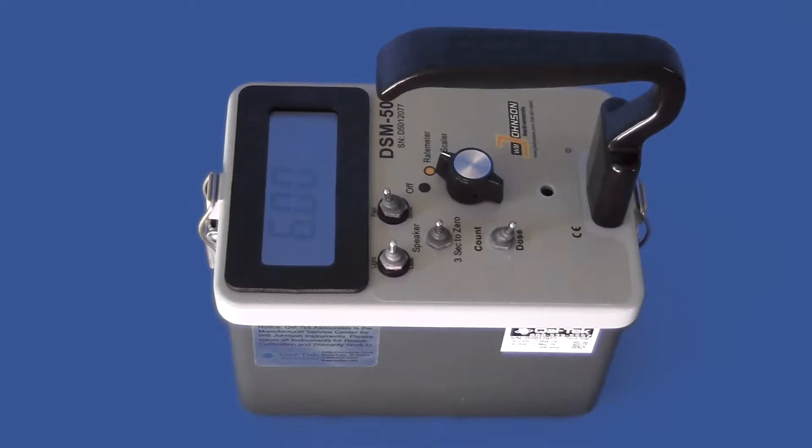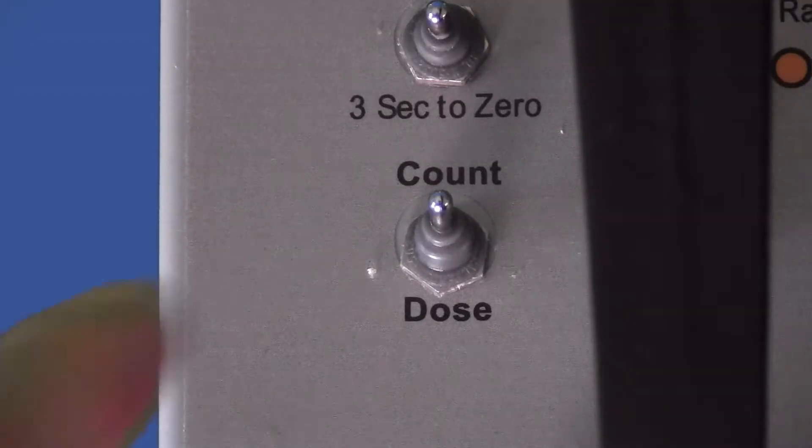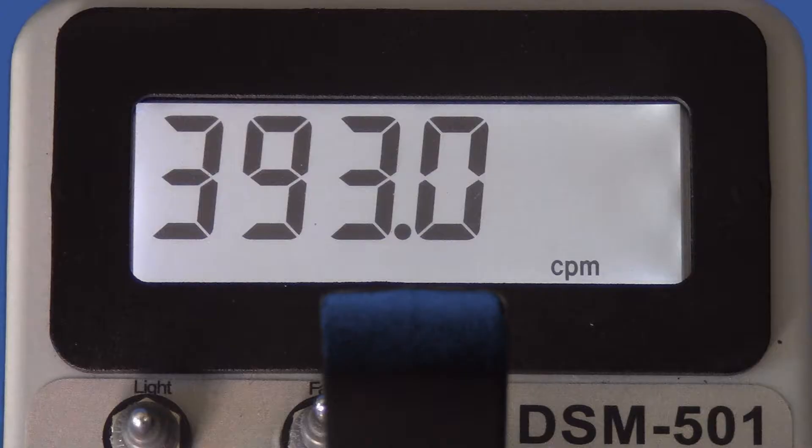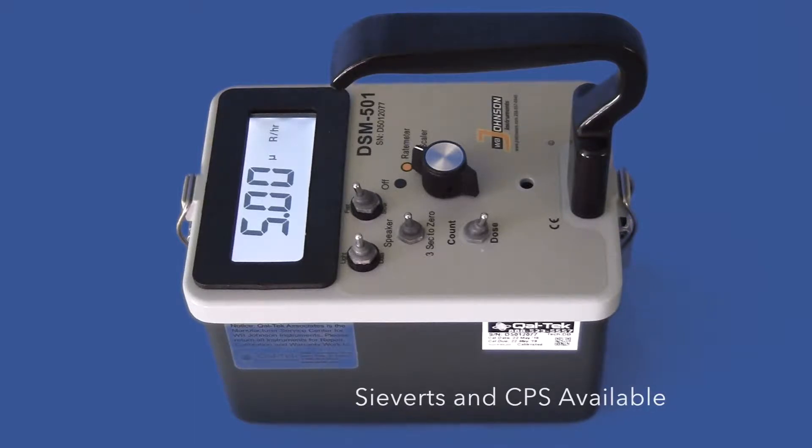Starting out in rate meter mode, we can turn on the meter face light by switching this control upward. This illuminates the display nicely for 30 seconds. The rate meter mode features dose in microroentgen per hour and counts in CPM, counts per minute. We can change easily to international units via an internal switch. We will demonstrate that later on in the video.